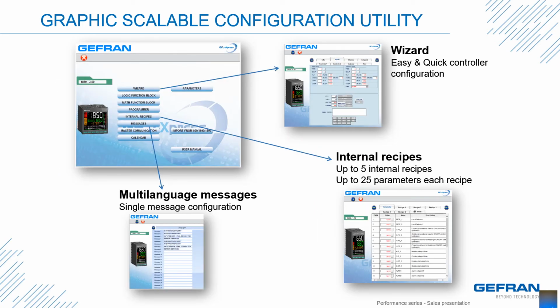Within the configuration tool, there is a quick wizard. It's nicely laid out with tabs and groups of settings, which has the most common variables and settings readily available for your use. The Express tool also lets you change to other supported languages. There's also a selection for you to preset up to 5 recipes with 25 parameters, making the unit easier to set and use at the plant floor.